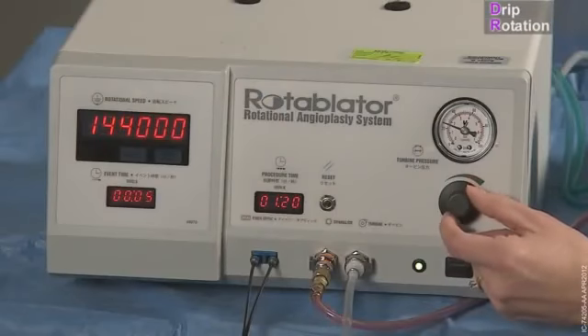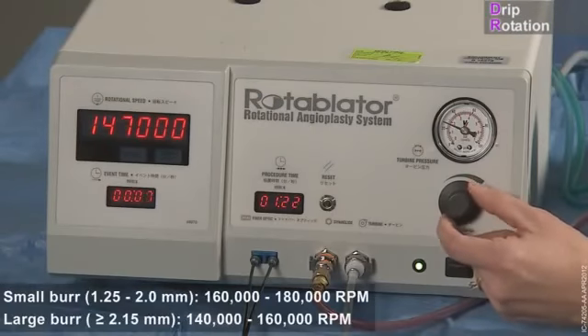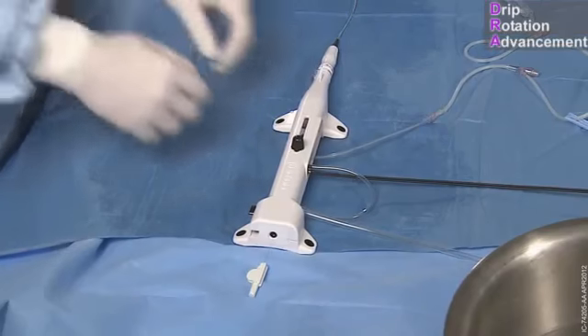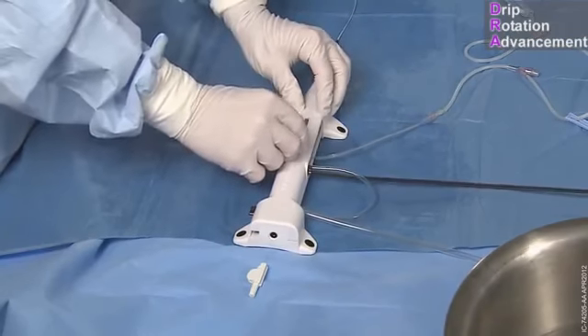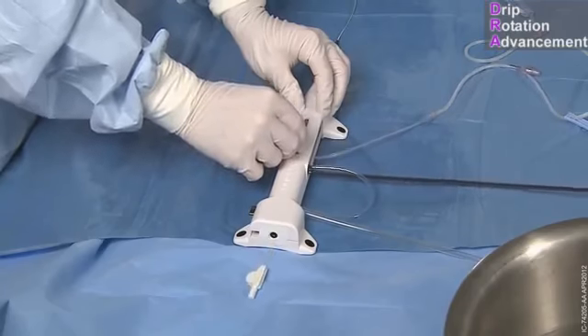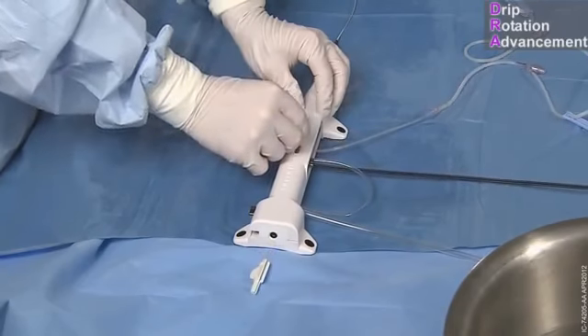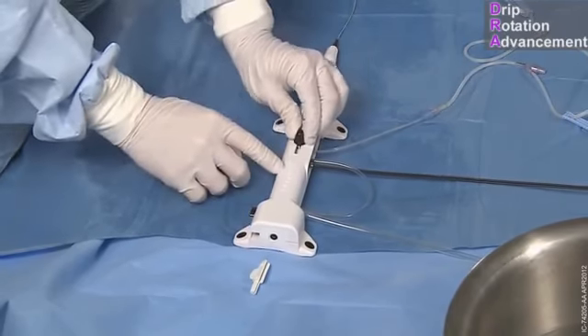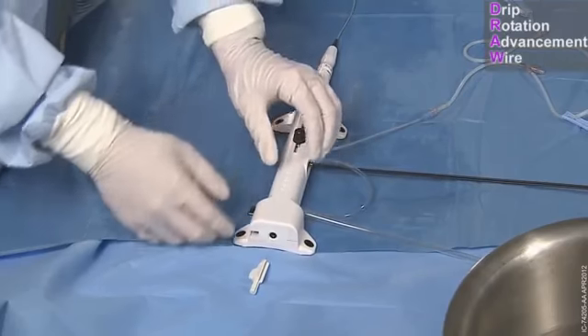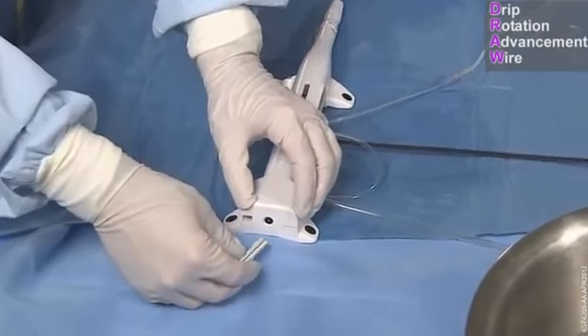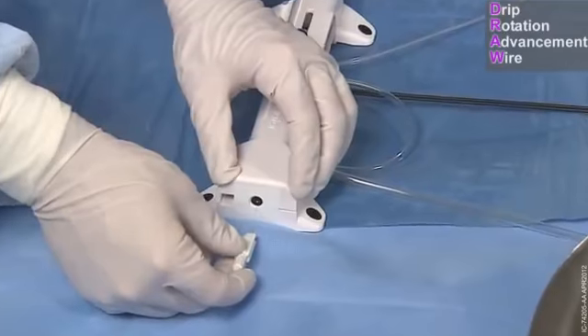Second, verify that the rotation speed of the burr is set at the desired rotation level. Then confirm that the advancer knob and burr move freely. Position the advancer knob approximately 1 inch from the proximal end of the advancer slot and tighten. Finally, verify the brake is holding the guide wire while the burr is spinning. The test is now complete.